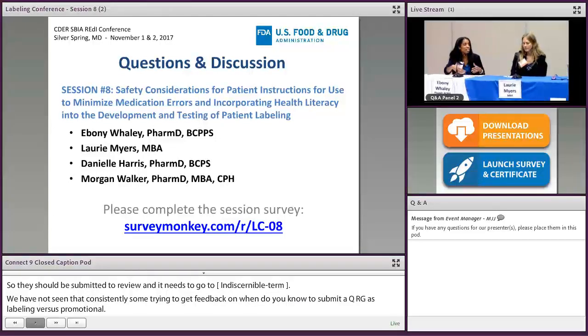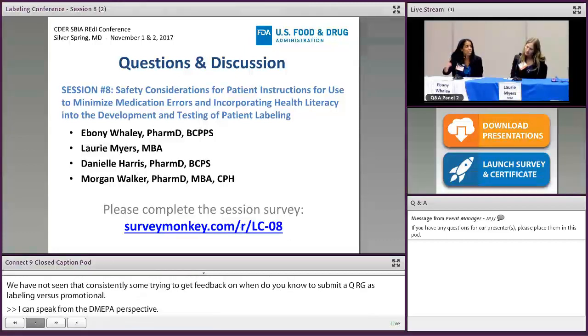I can speak from the DMEPA perspective. For a QRG, we consider it as part of the user interface. So we expect that if you did conduct a human factors testing, that it's included as part of that user interface in the testing as part of the overall labeling.